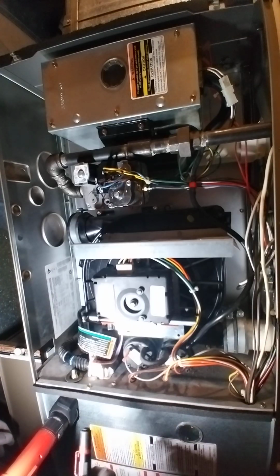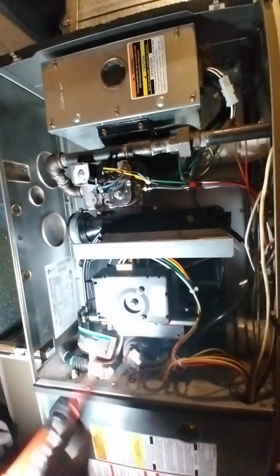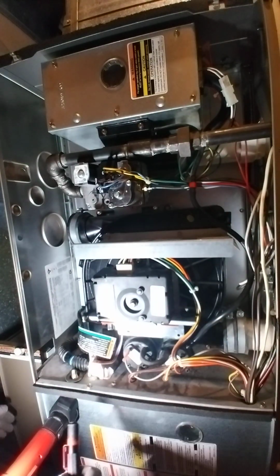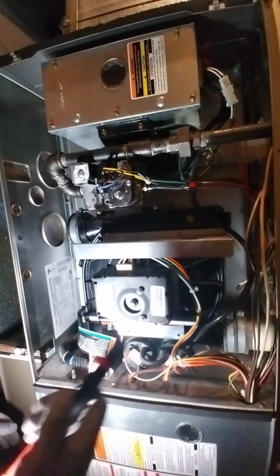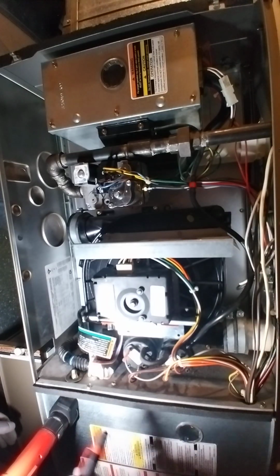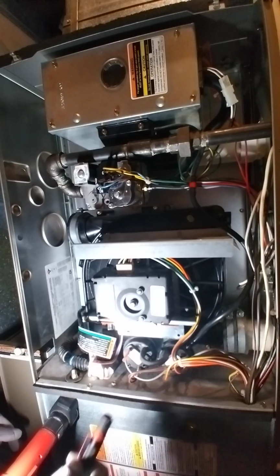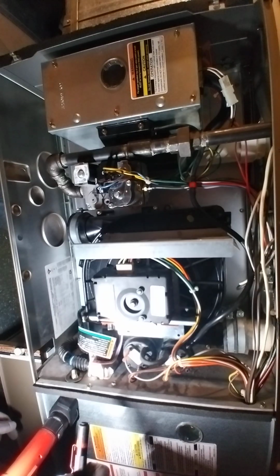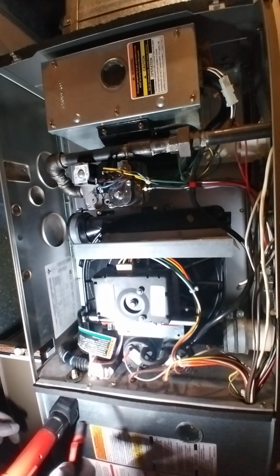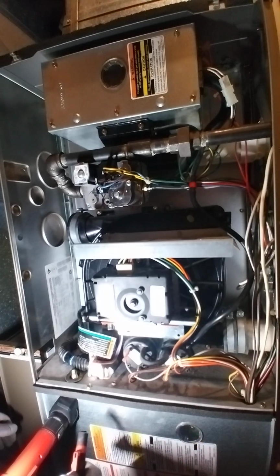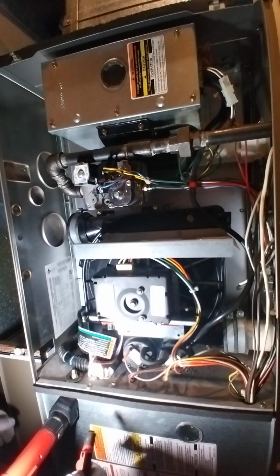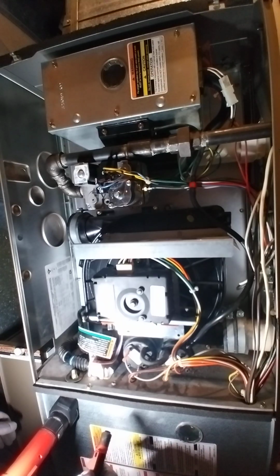So I started wondering, well, maybe the switch is starting to go bad or something like that. But when I started reading through the manual, I found out that luckily most furnaces, I assume, have a diagnostic mode where you flip a dip switch on the control board, which is hidden behind here, and it'll flash a series of LEDs in a way that leads you to a certain part of the maintenance manual. Kind of like the old diagnostic systems on cars where you hook up a 12-volt lamp and jump a couple of wires and it starts flashing at you what error codes it was.